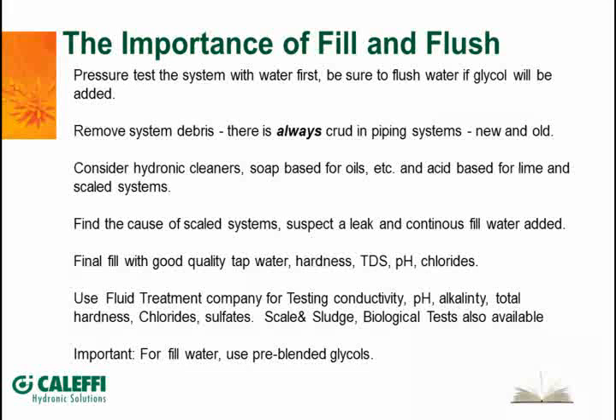I just put a new Lochinvar boiler in my own house, and I know they gave me, I think, three things in there. They said the chloride's less than 200 parts per million, less than 7 grains on the hardness, and I think there's also a spec in there on the pH. So they're going to give you an idea of what they want because, again, they're aware that with these smaller heat exchangers you've got to be pretty close on your water or things can go bad pretty quickly.